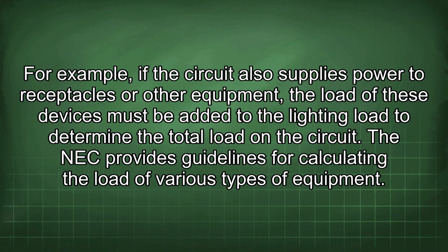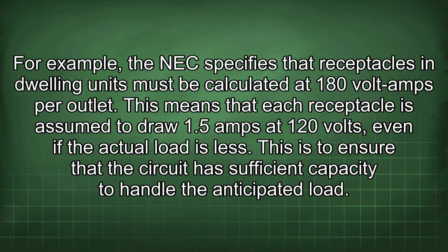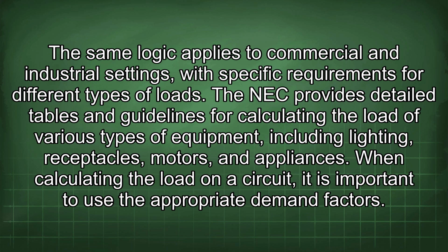The NEC provides guidelines for calculating the load of various types of equipment. For example, the NEC specifies that receptacles in dwelling units must be calculated at 180 volt-amps per outlet. This means that each receptacle is assumed to draw 1.5 amps at 120 volts, even if the actual load is less. This is to ensure that the circuit has sufficient capacity to handle the anticipated load. The same logic applies to commercial and industrial settings, with specific requirements for different types of loads.